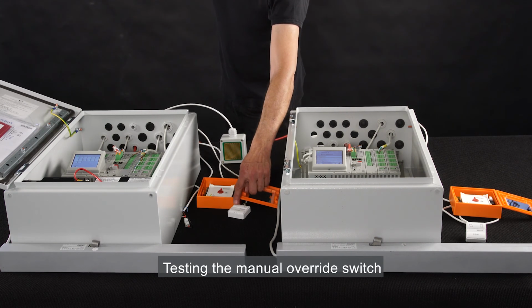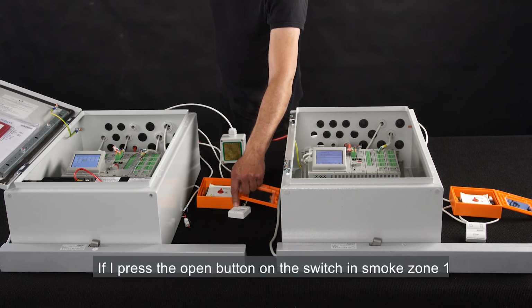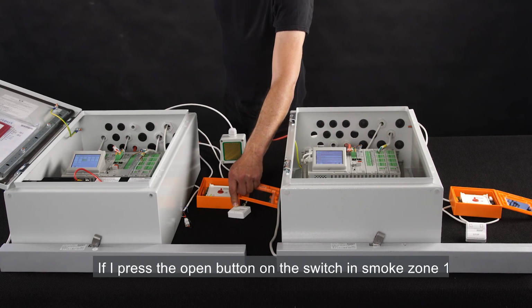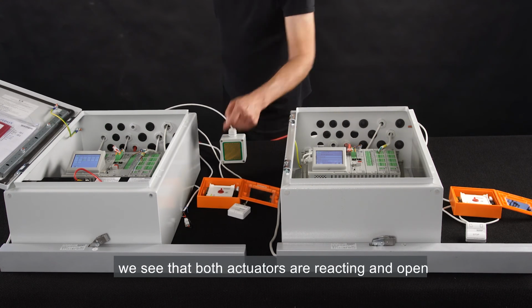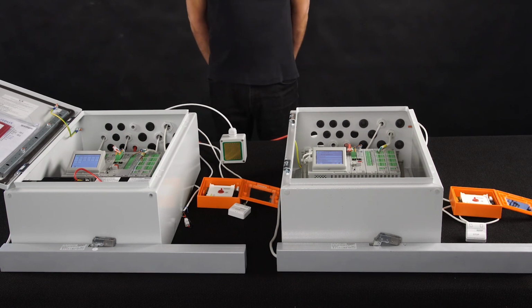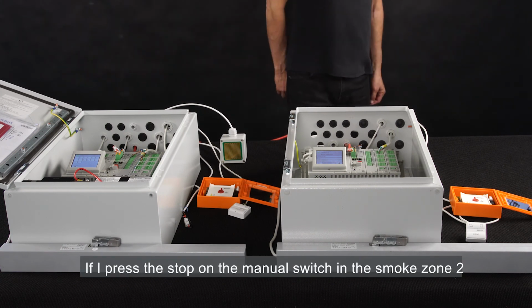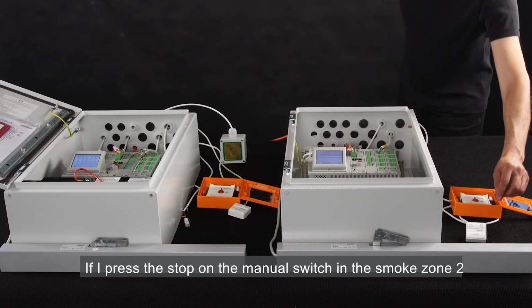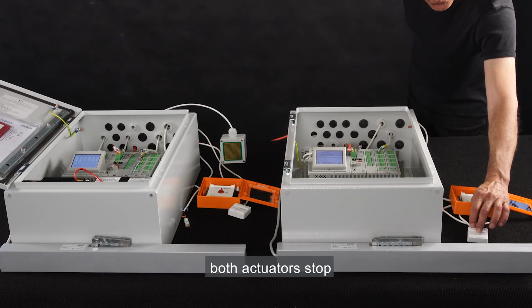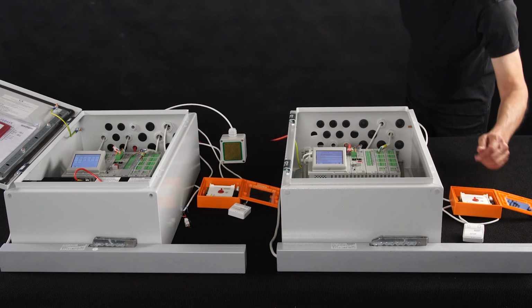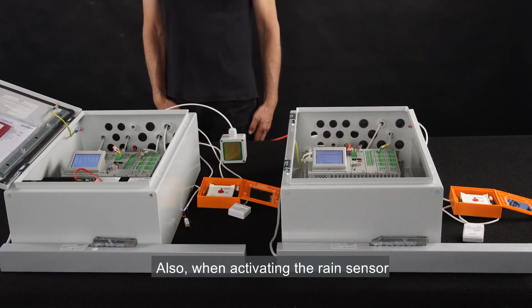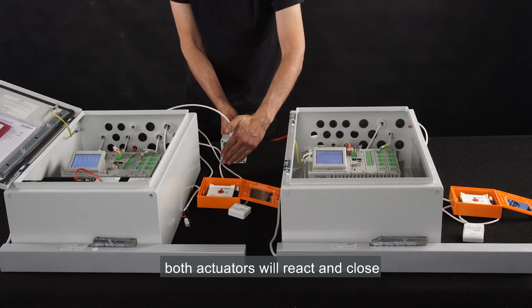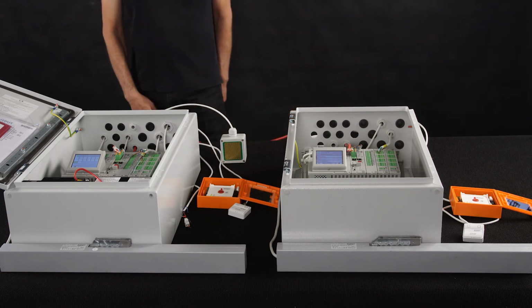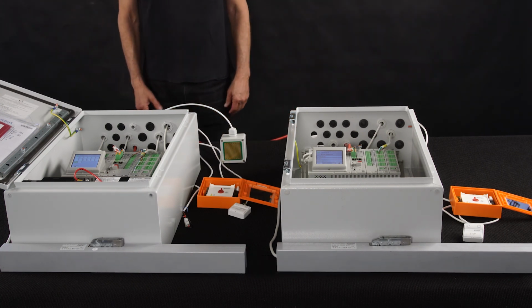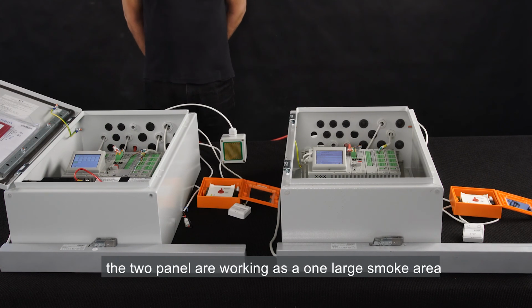Testing the manual override switch. If I press the Open button on the switch in Smoke Zone 1, we see that both actuators are reacting and open. If I press the Stop on the manual switch in the Smoke Zone 2, both actuators stop. Also, when activating the rain sensor, both actuators will react and close. As you can see, the 2 panels are working as one large smoke area.